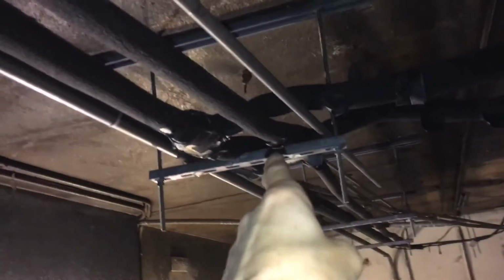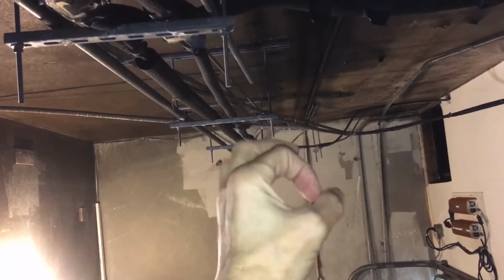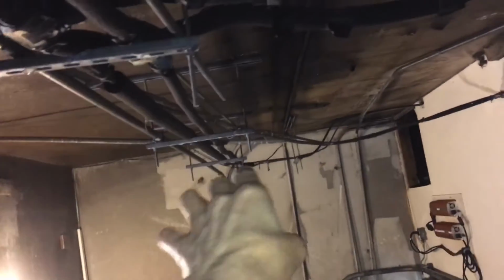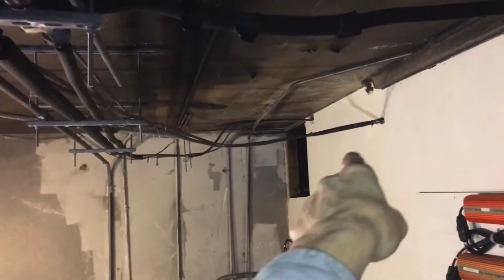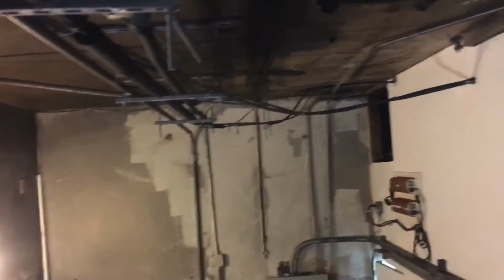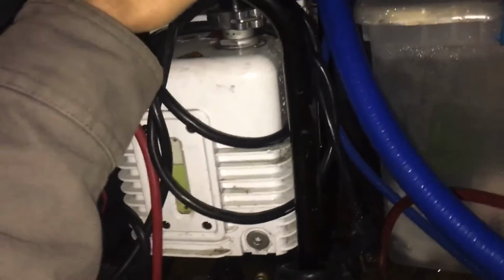And then if you keep on following it down, there's another Y branch right there, and it goes off to another air handler. There was a fire in here, so that's why the insulation looks a little funky. It kind of melted. And then at the very last air handlers, we used the white insulation. That's the, you know, that rolls of the white. Forgot the name of the stuff. But when the fire was in here, it completely shrunk down like shrink wrap around the copper pipes. And so we'll get back to this story when it'll at least be on the vacuum pump or 2 vacuum pumps for 24 hours or more.